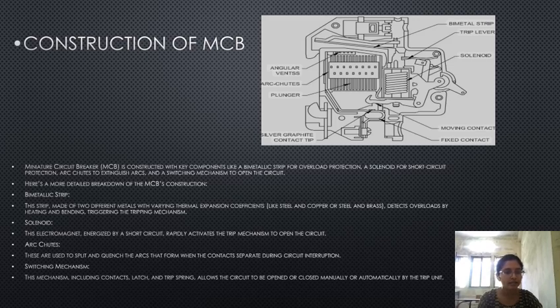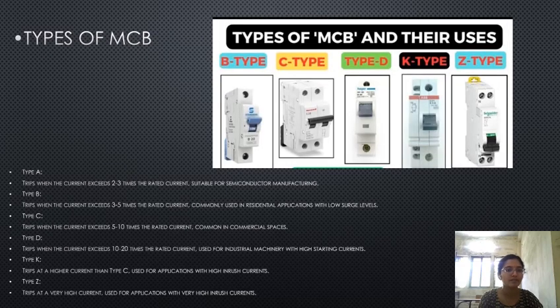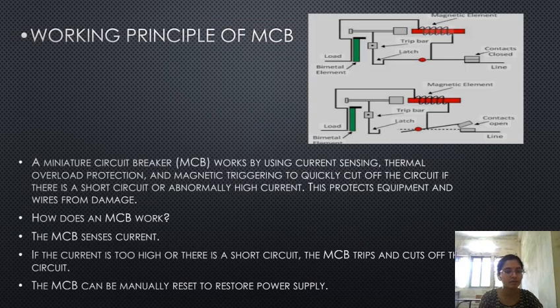Here is a more detailed breakdown of MCB's construction. Bimetallic strip. The strip, made of two different metals with varying thermal expansion coefficients, detects overloads by heating and bending, triggering the tripping mechanism. Types of MCB. Here we can see there are types like type A, type B, type C, type D, type K and type Z. Working principle of MCB. A miniature circuit breaker works by using current sensing, thermal overload protection, and magnetic triggering to quickly cut off the circuit if there is a short circuit or abnormally high current. This protects equipment and wire from damage.